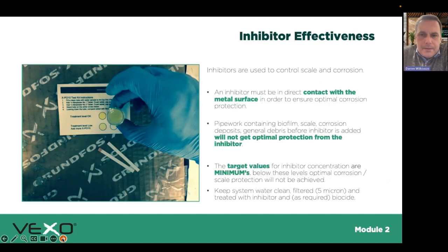So if you are using inhibitors, leaning more towards the BSRIA approach, we need to make sure it's effective. For it to be effective, we need a clean system so we can get to the full metal surface, free of pipework scale, biofilm and so on. Otherwise we're simply not going to get the level of protection. And importantly, we want to make sure we're maintaining the right level of inhibitor.